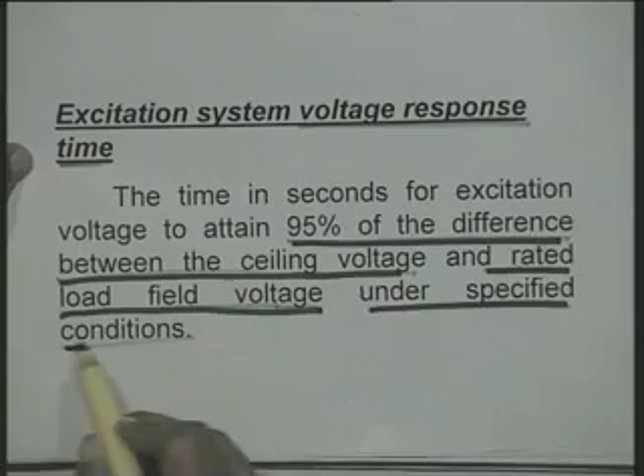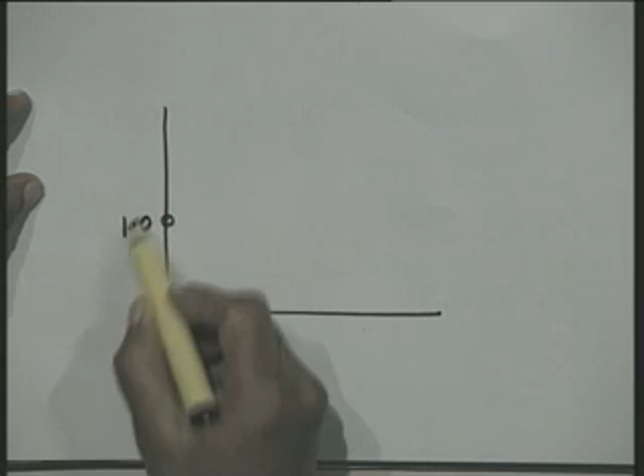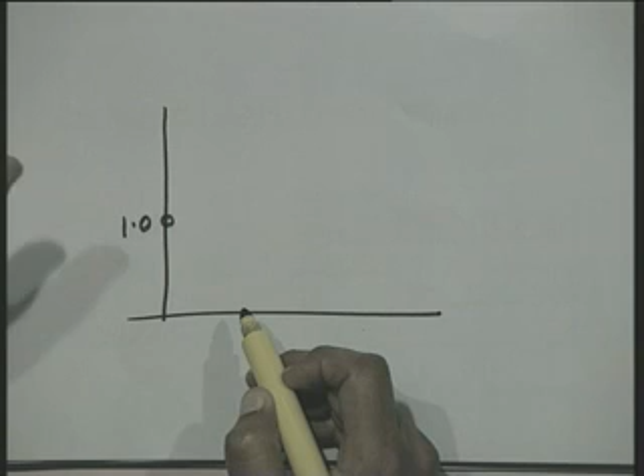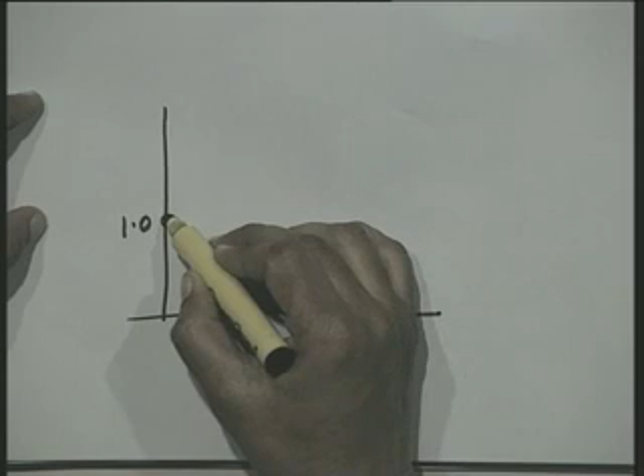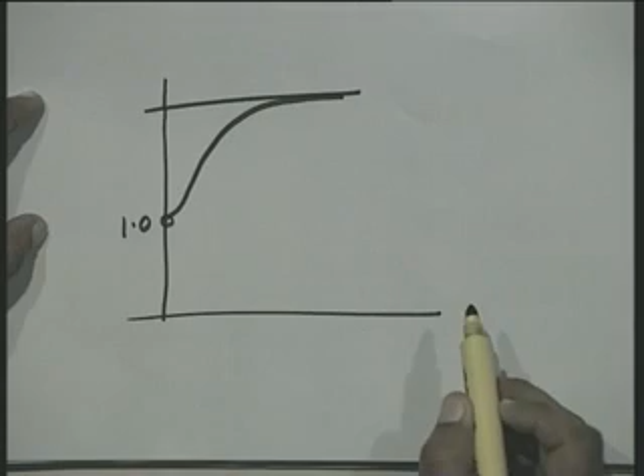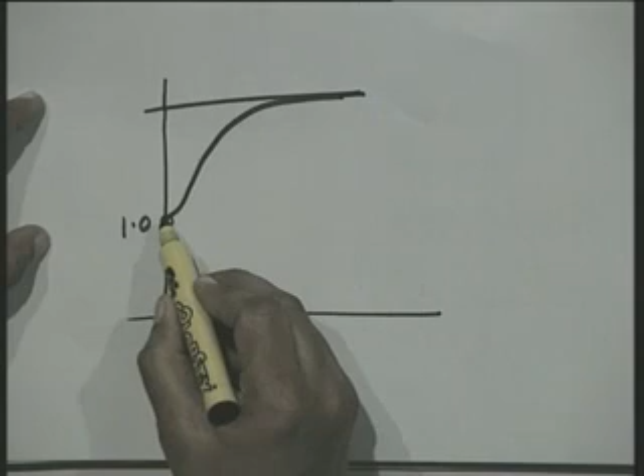Now, to quantify the voltage response, we define a voltage response time. The time in seconds for the excitation system voltage to attain 95% of the difference between the ceiling voltage and the rated load field voltage under specified conditions. Just to illustrate this, suppose this is the rated voltage, let us say it is 1.0. If I create terminal conditions or the voltage regulator operates in such a fashion that voltage is made to increase in this fashion, and let us say that this is the ceiling voltage. Then we find the difference between the ceiling voltage and the rated voltage, and the time which is required to attain 95% of this value.